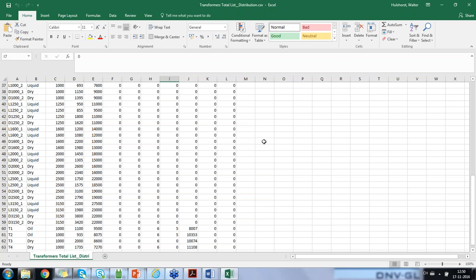So if you know that the extra losses are also important for the harmonic losses, you can imagine that the transformer with a higher impedance normally has higher losses compared for the harmonics. But it depends a little bit on the design. But I said it's just a generic answer what I can provide. We can also imagine that in case someone is making a transformer with a high impedance and he's still using CTC wires compared to a transformer with a lower impedance but using just a single wire, then it definitely will make a huge impact on the harmonics for the transformer with the low impedance, because the eddy currents will be higher in that situation. But if they use the same material and the same kind of winding arrangement, then normally the transformer with a high impedance has higher losses, additional losses, sorry.